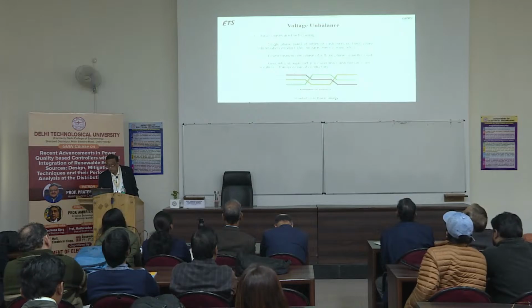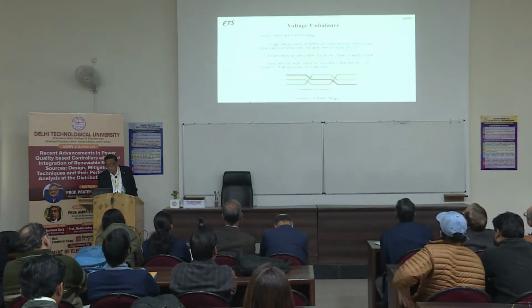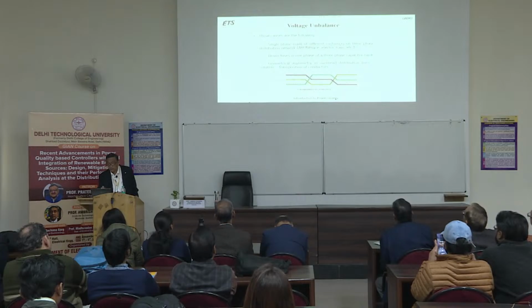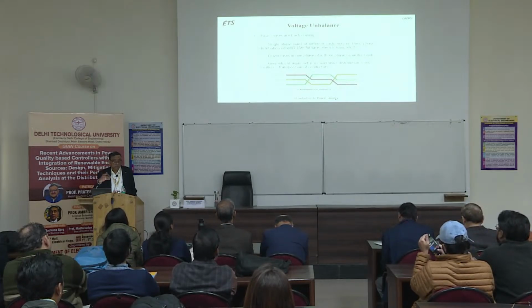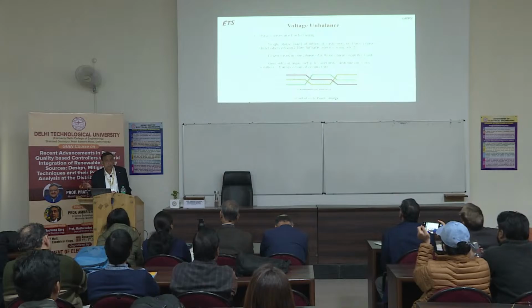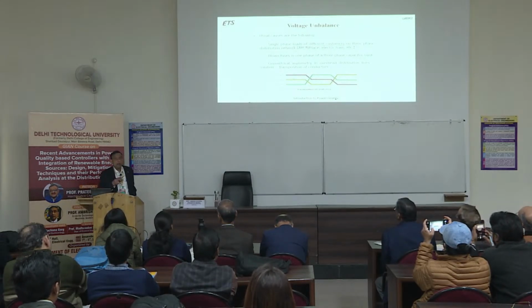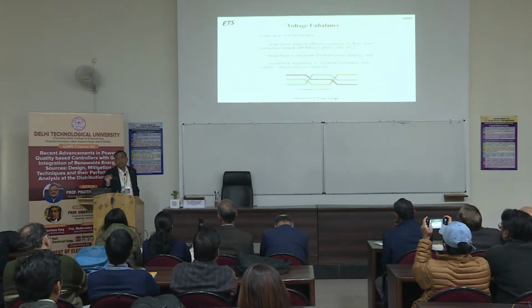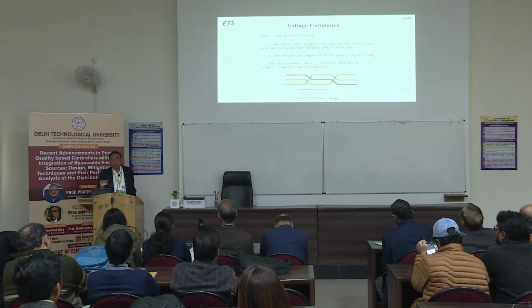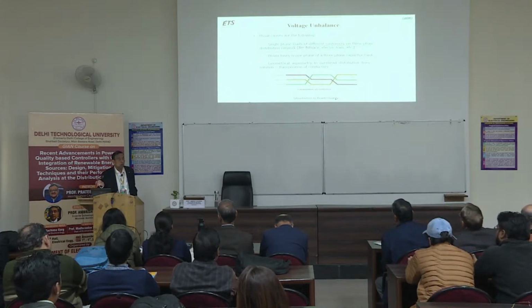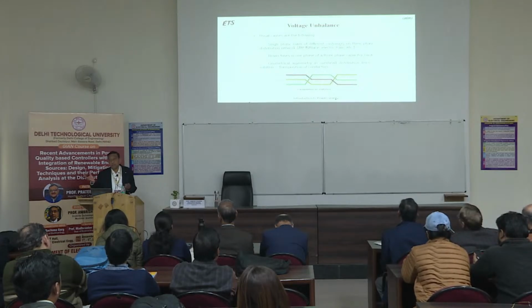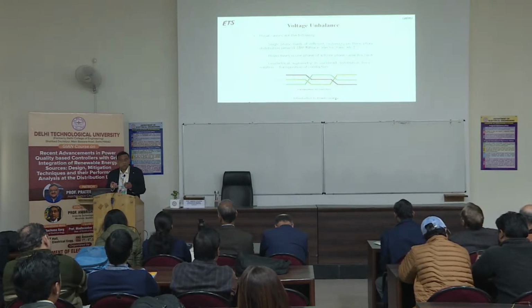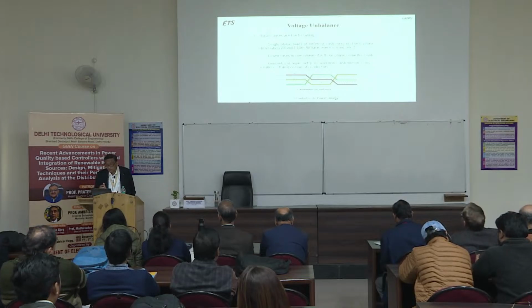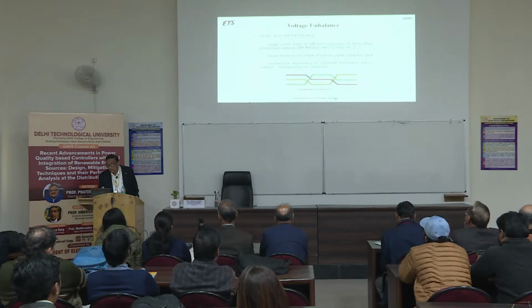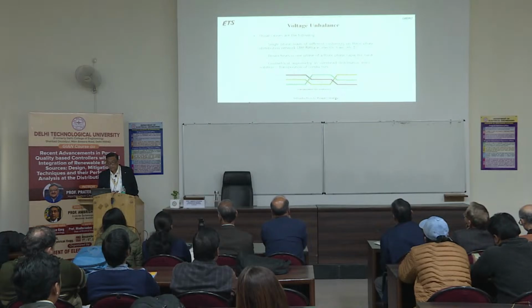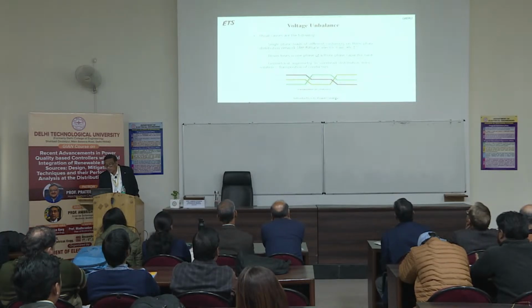Usual causes of voltage unbalance: single phase loads of different customers on a three-phase distribution network. Like sometimes it happens in our building, also in my institute, that different floors are coming from different phases, so they may not have equal load. That is single phase load on a three-phase system, different loads, so it may cause voltage unbalance, or it may be caused by an arc furnace or electric train, etc. Another cause is blown fuses in one phase of a three-phase capacitor bank.